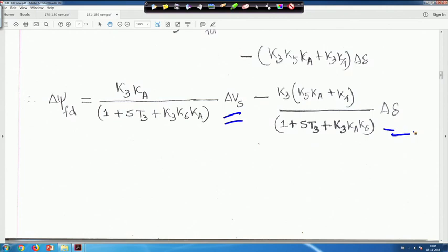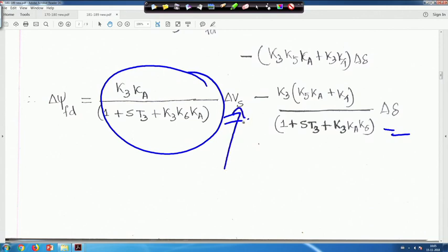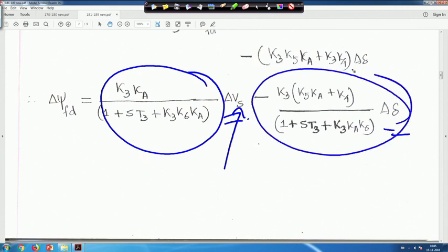So now this term has come into this equation because of the power system stabilizer delta Vs, right. Earlier, if it is not there, previously this term was there, right. But in that case you have to neglect TR, you just neglect TR and do not consider delta Vs, then you will see this term is there. But due to delta Vs, this term has been introduced, right. So that means we have to see that it is providing damping. That is why this term is there, and this is the output signal from the stabilizer, delta Vs, right.